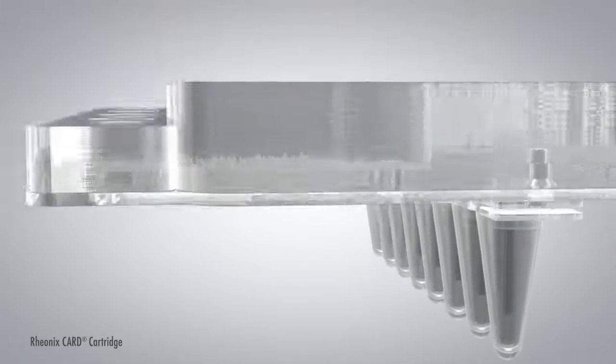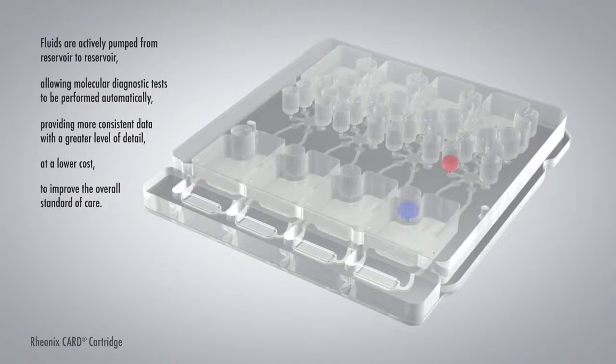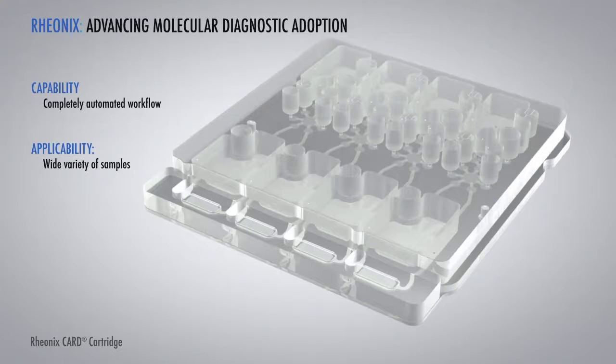The upper surface of the card contains reservoirs that hold reagents used in the extraction, purification, amplification, and detection process, and any resulting liquid waste. The channels and pumps located on the lower surface of the card are used to transport and mix reagents and move wastes into the reservoirs on the top surface.